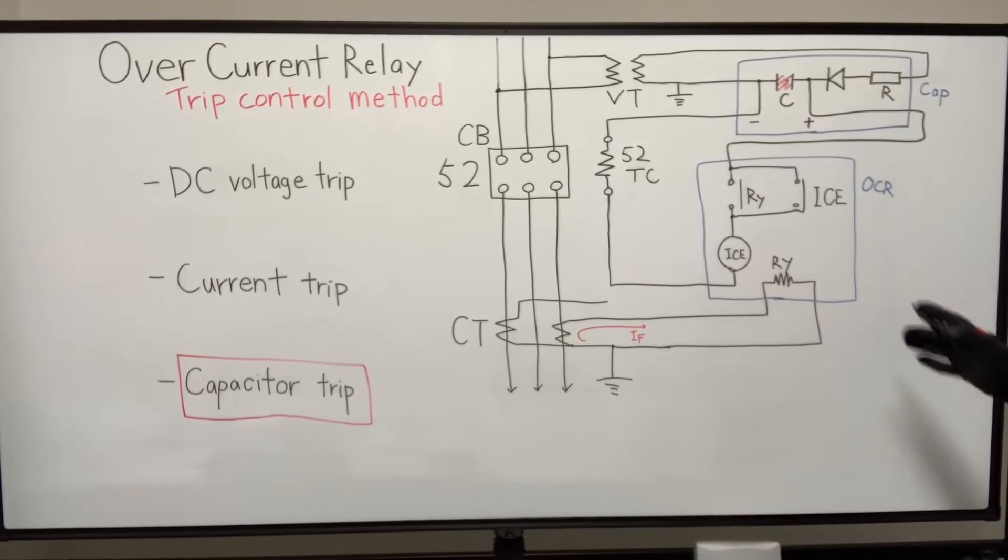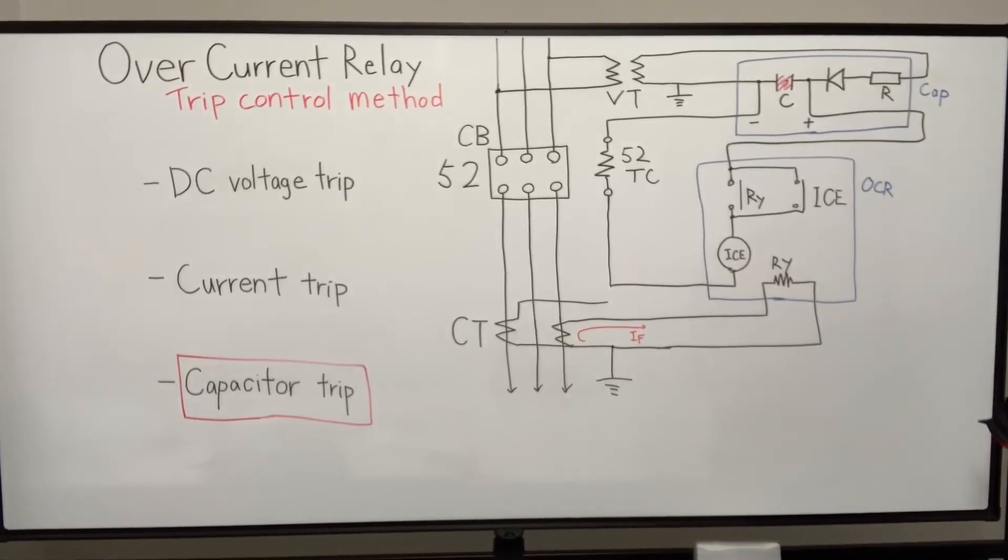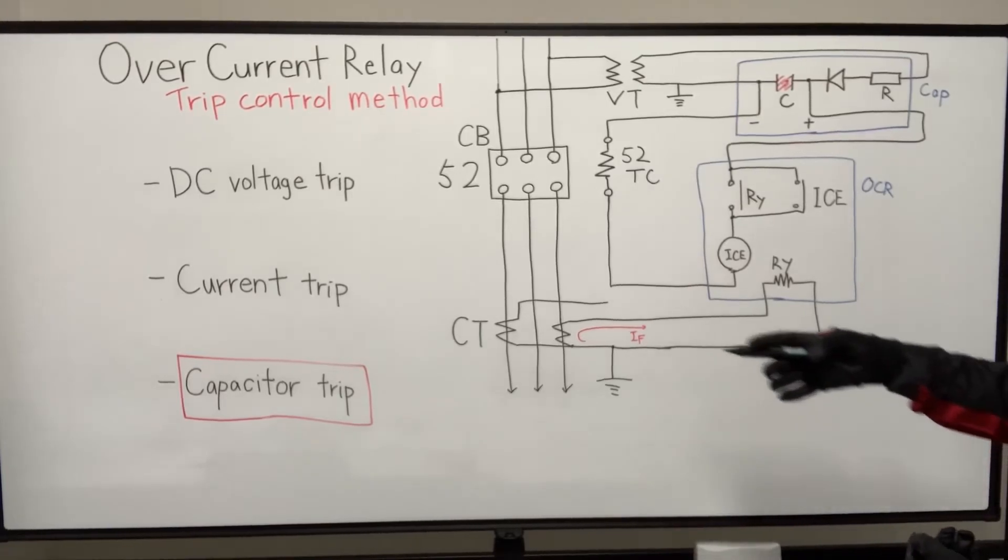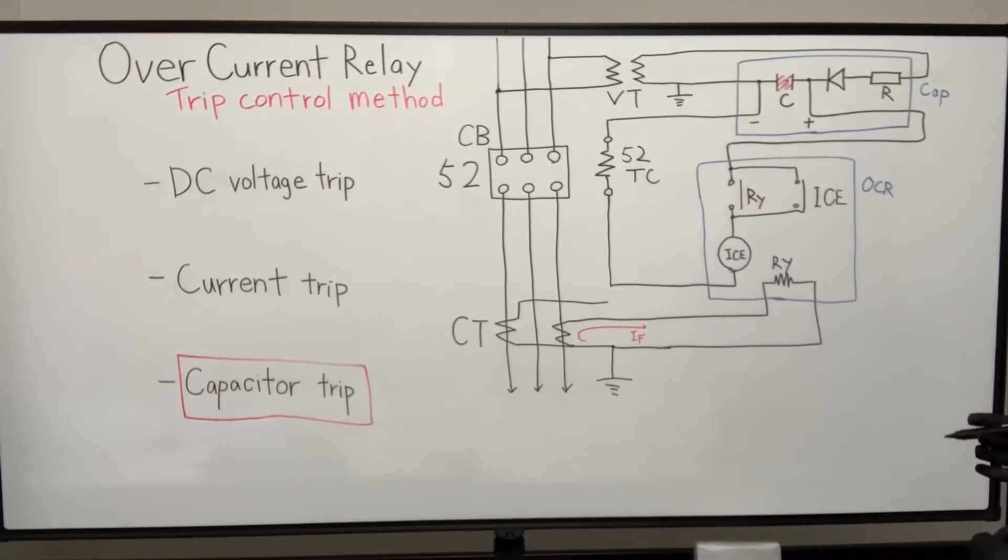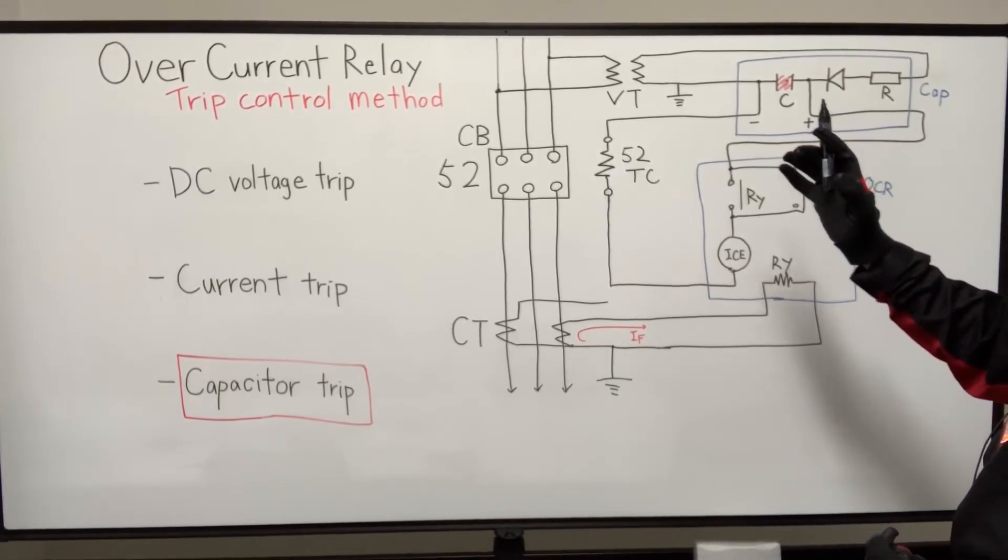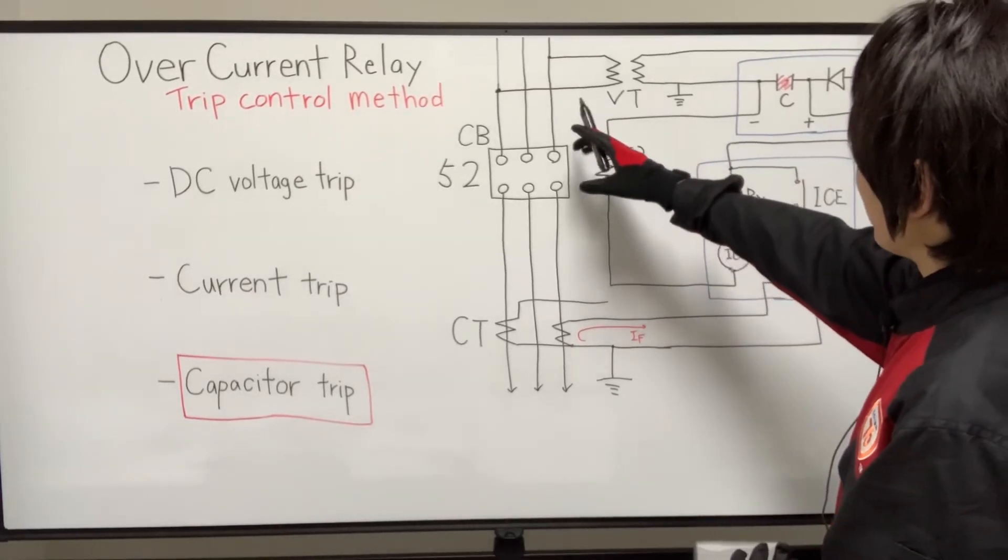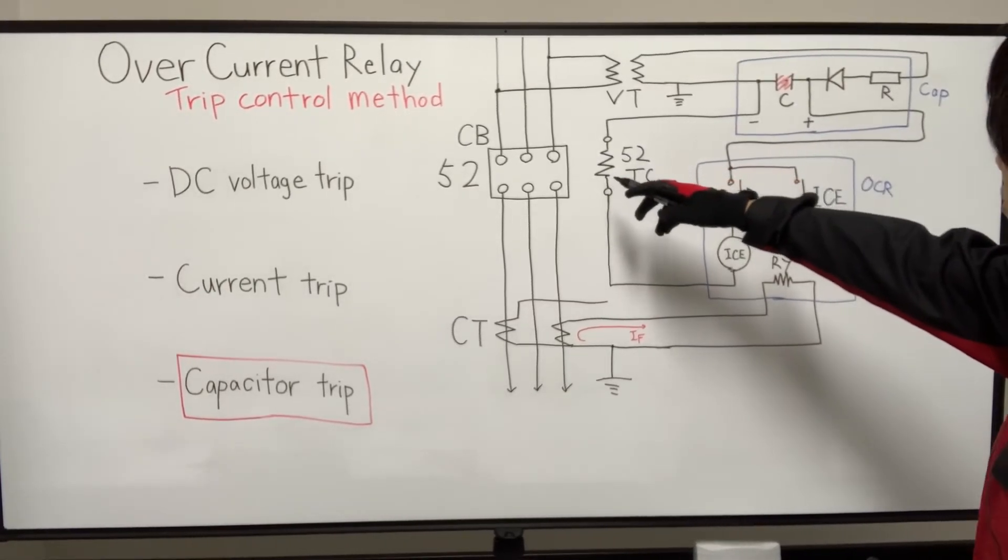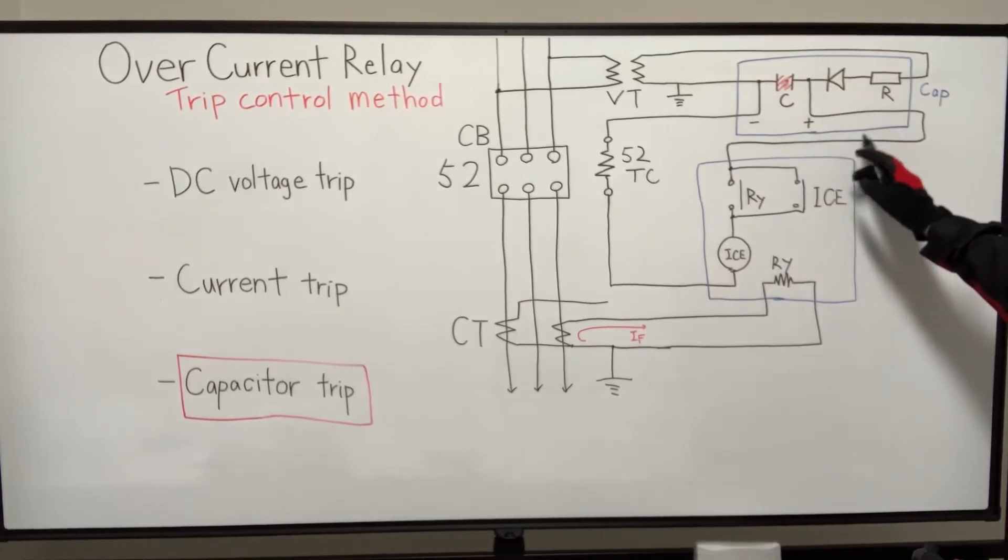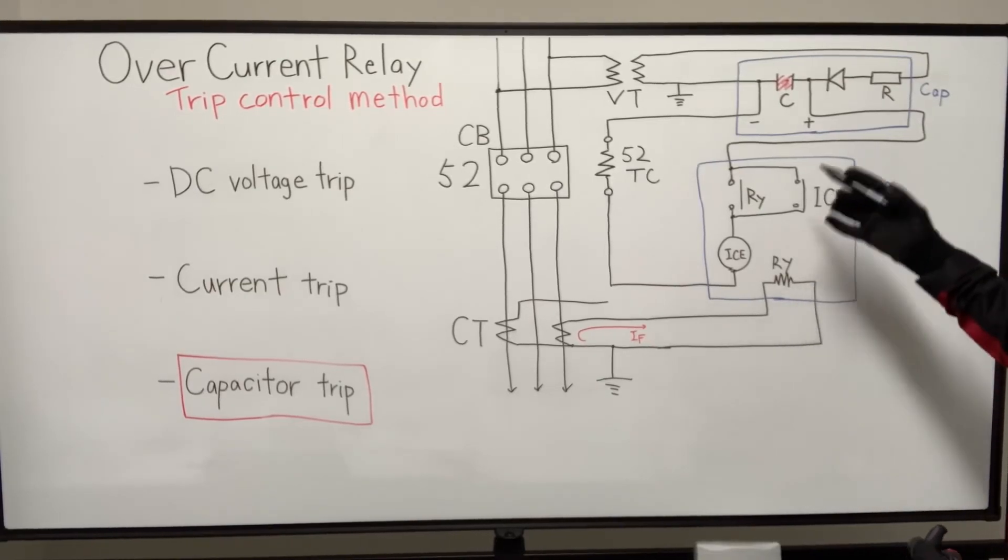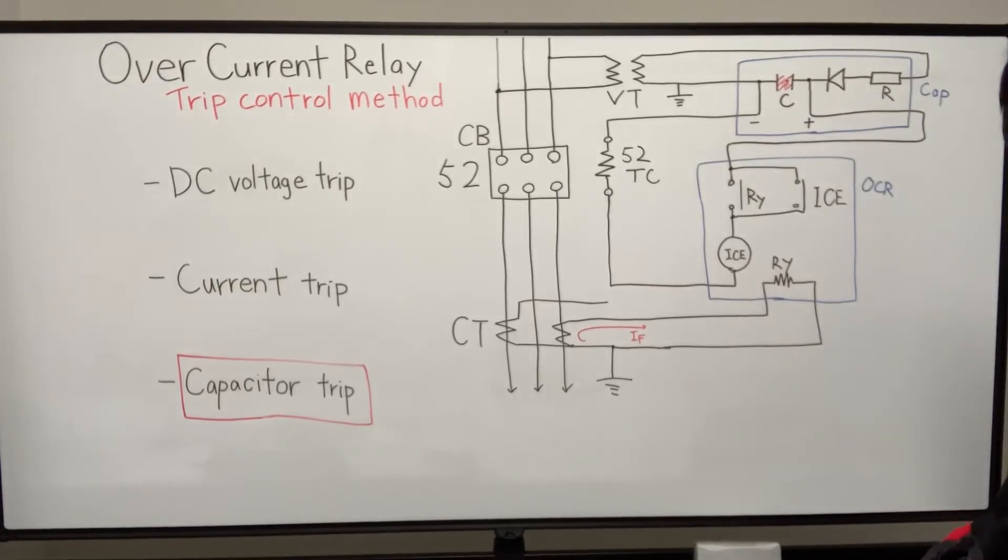And in this manner, there are no need to install some external power supply. So it's cheaper, relatively cheaper, like compared to DC voltage trip. And also, if the power outage happens at the main power system, it still has the capability of tripping circuit breaker by using this charge of the capacitor, one time or several times, as long as this charge of the capacitor exists.